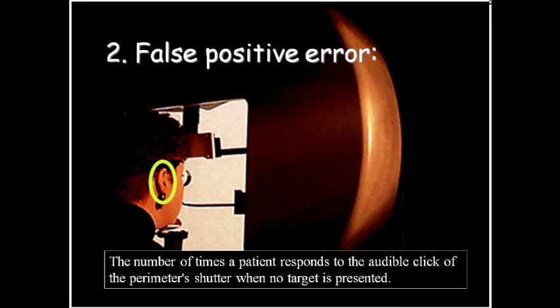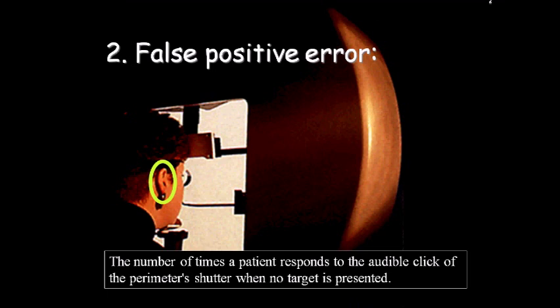False positive error: when putting the stimulus, the machine makes an audible sound, and the patient may learn to respond to that sound. To avoid this problem, in between stimuli the machine will send the audible sound without any stimulus. If the patient responds that he sees the light, we call this a false positive — the patient is responding to something he thinks he sees, although there is no visual stimulus, only an audible one. Again, this number should be less than one-third of the times tested.